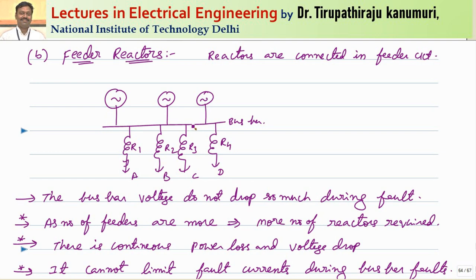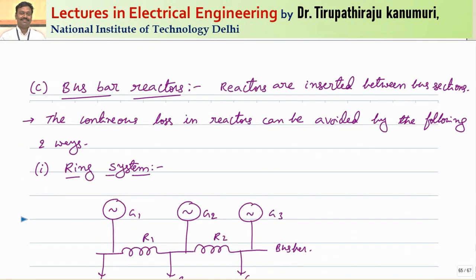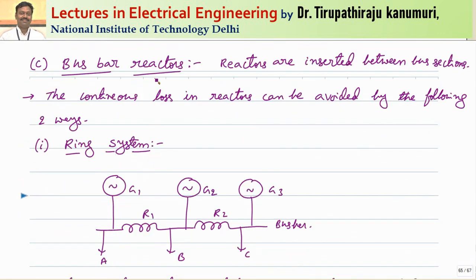However, feeder reactors still have the disadvantage of continuous power loss and voltage drop, since each reactor continuously carries rated current. Another disadvantage is that if the fault happens on the bus bar itself, the feeder reactors cannot protect the generators during a bus bar fault. Although bus bar faults are less frequent, feeder reactors do not provide protection in that scenario. That is why this method is not used in practice, and instead we go for bus bar reactors.